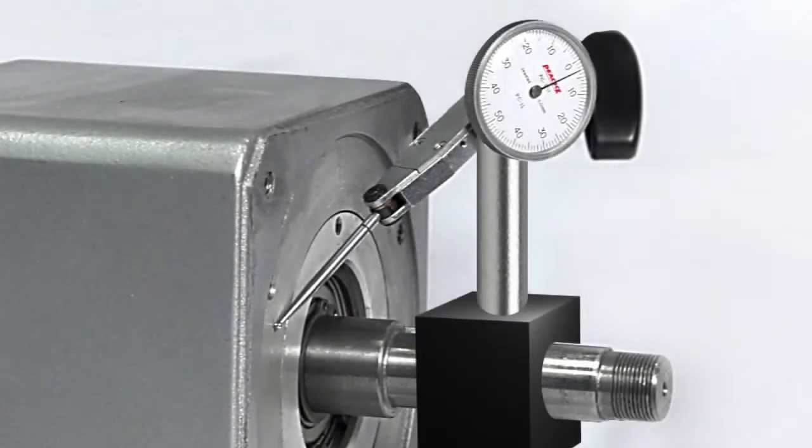The next thing to check is the pilot and bolt circle. These should be concentric to the shaft within six-thousandths total indicator runout.